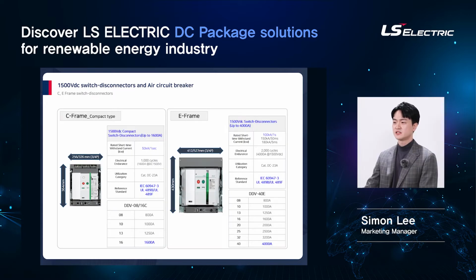Among various types of DC switches, two types are the most common: compact type and E-frame DC switch. Compact type is only up to 1600 ampere frame, while E-frame is up to 4000 amps, and both are UL and IEC certified.